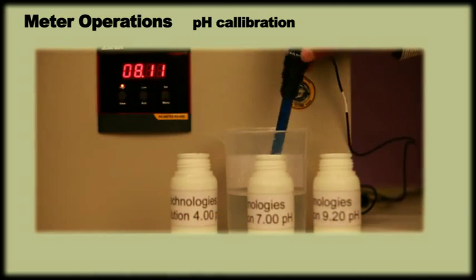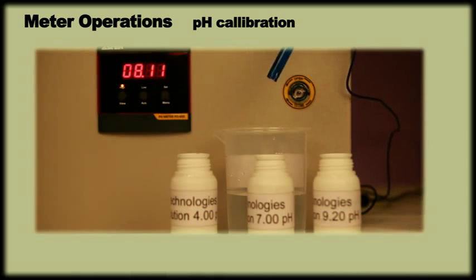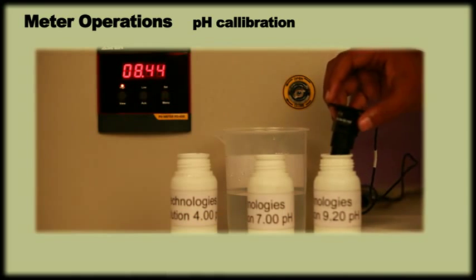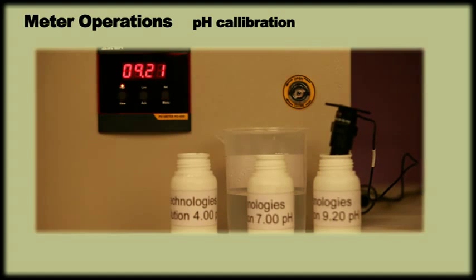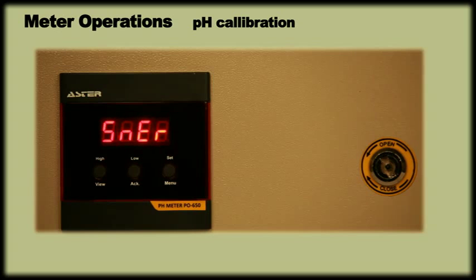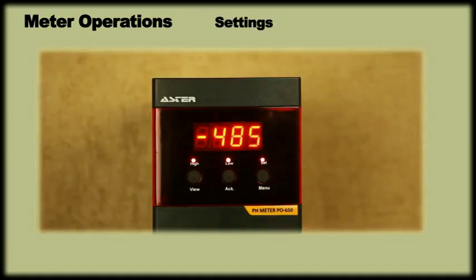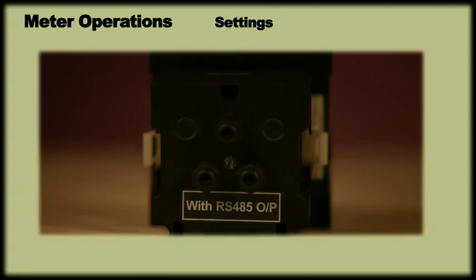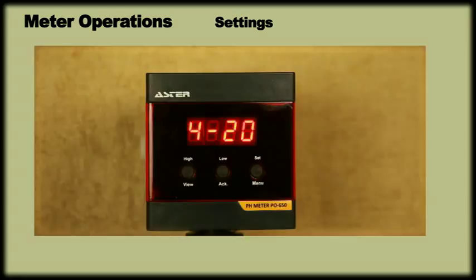In order to cross-check the calibration settings, the meter has a third point checking facility. Please note that if the actual reading for 0 and span differ by 40%, then the meter will show sensor error and start showing readings as per previous calibration. As mentioned earlier, the meter is available with an optional output of both RS485 and 4 to 20 mA. Let us first understand the settings for 4 to 20 mA.